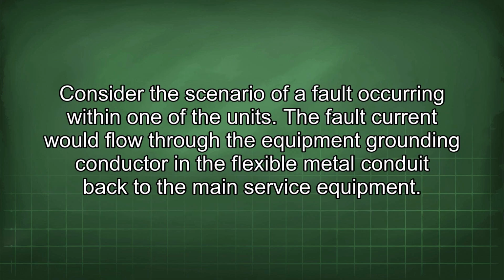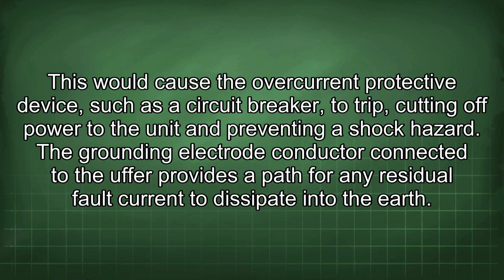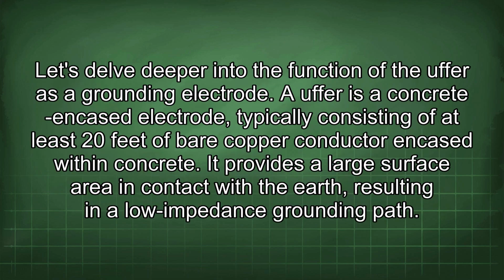Consider the scenario of a fault occurring within one of the units. The fault current would flow through the equipment grounding conductor in the flexible metal conduit back to the main service equipment. This would cause the overcurrent protective device, such as a circuit breaker, to trip, cutting off power to the unit and preventing a shock hazard. The grounding electrode conductor connected to the Ufer provides a path for any residual fault current to dissipate into the earth. Let's delve deeper into the function of the Ufer as a grounding electrode.